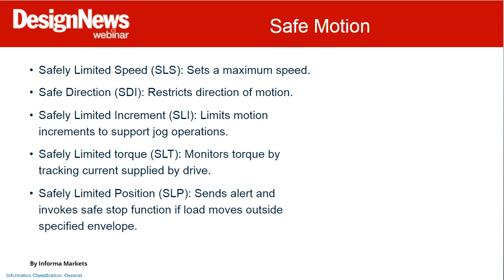Cleaning activities -- this is rollers in a paper plant. The old way: shut everything down, go in the enclosure, clean a little bit that you can reach, step out, turn it on, jog it, turn it off, go back in, rinse, repeat. Takes forever. The new way, with functional safety, you can use safe direction and safe speed, which lets you clean continuously and remain safe. Machine builders are designing cleaning modes that do this kind of stuff automatically, so the equipment spends more time producing and less time being maintained.